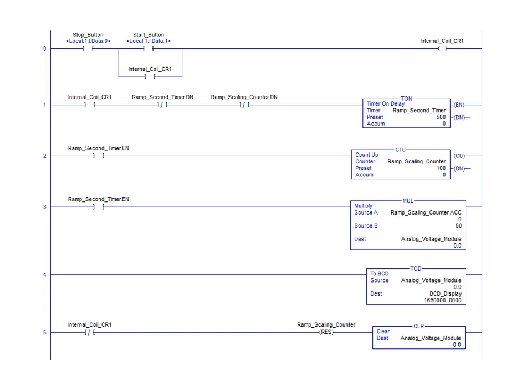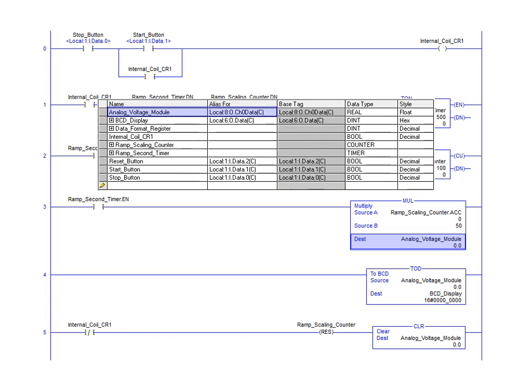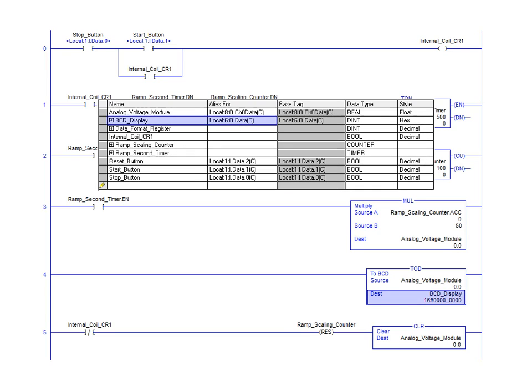We have added rung 4 to the application, allowing for the value being sent to the analog voltage module to be displayed on the slot 6 BCD output display. As can be seen here, the analog voltage module tag is an alias for our slot 8 channel 0 output location. This location will receive values from 0 to 5000 and translate them to output voltages between 0 and 10 volts. The BCD display tag is an alias for the slot 6 BCD output display.